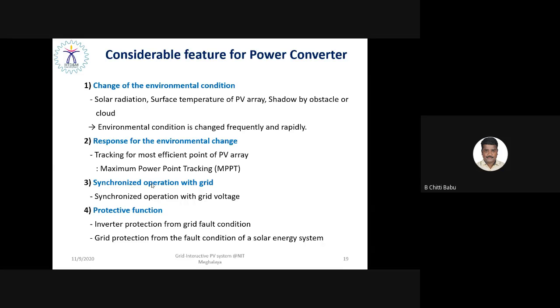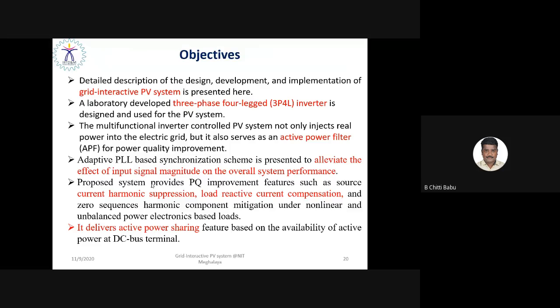And synchronized operation with the grid is a very important concern while integrating a solar PV system with the utility grid. The protective function, inverter protection from grid fault conditions and grid protection from fault conditions of the solar energy system, is of great interest. It should be further investigated. So nothing is straightforward. Simply using the converter doesn't mean you are integrating a solar PV system with the utility grid. It has different challenges, and those challenges have to be defended against with the help of the power converter control, right?